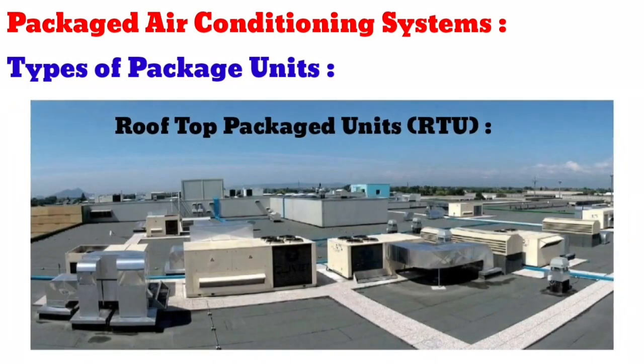Rooftop package units, or RTUs, are installed on the roof and air is blown downwards through the ductwork. The units are set on curbs that are flashed into the roof. Typical cooling capacity ranges from 3 to 50 tons. These are very commonly used in single storey structures, especially warehouses and superstores.